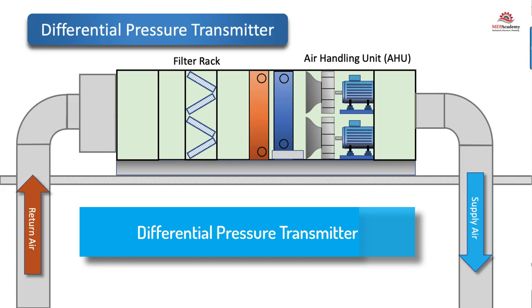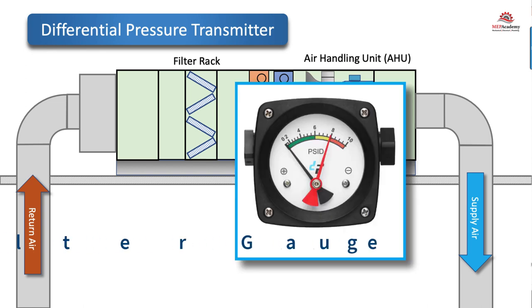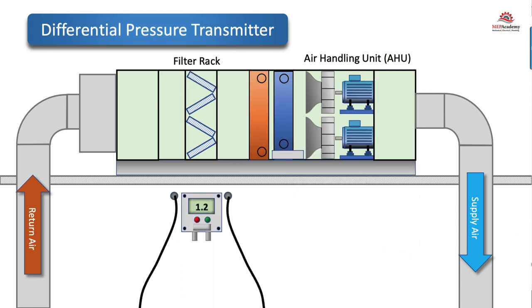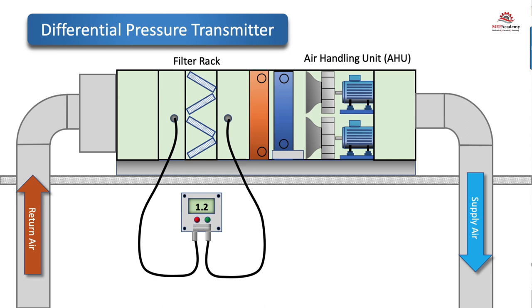Differential pressure transmitter for dirty filters. Differential pressure is used to indicate when filters have become dirty. When the filters are clean, there is less pressure drop across them. As dirt becomes trapped on the filter media, the pressure drop across the filter increases, which increases the differential pressure. By putting a differential pressure transmitter in place, an alert can be sent to facility personnel to change the filters. Increased pressure drop across the filter causes an increase in fan energy and utility cost.